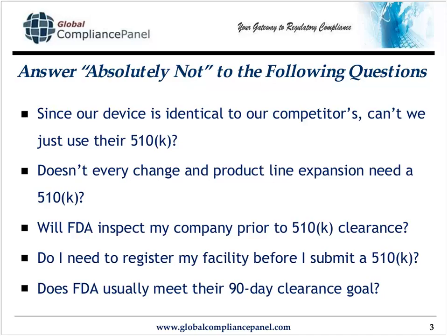Third question, more of a reasonable question, but still a question I've been asked: will the FDA inspect my company prior to 510K clearance? That's less, absolutely not, and more, not necessarily. Fourth, do I need to register my facility before I submit a 510K? And the last question is more laughingly asked than anything else, which is, does the FDA usually meet their 90-day clearance goal?